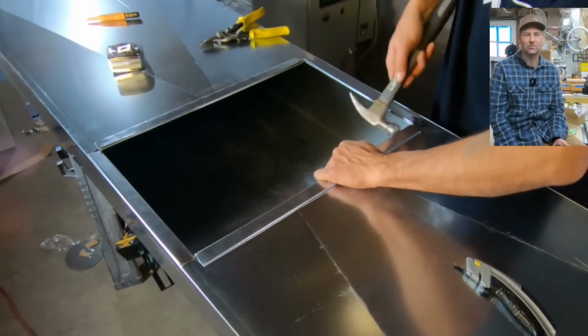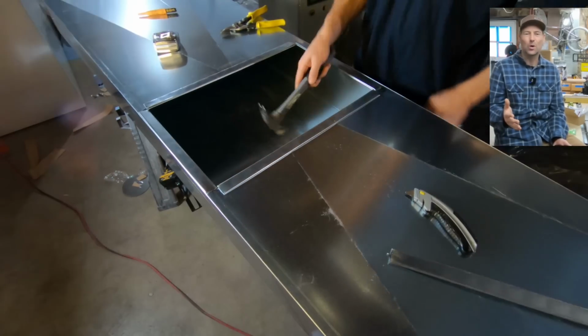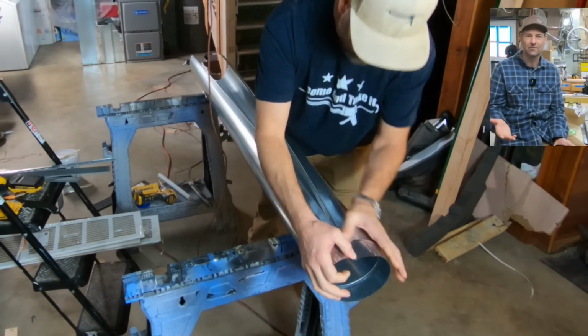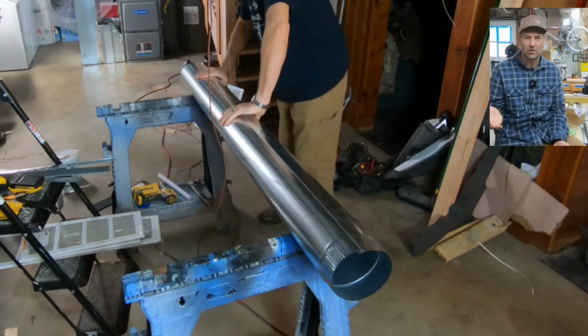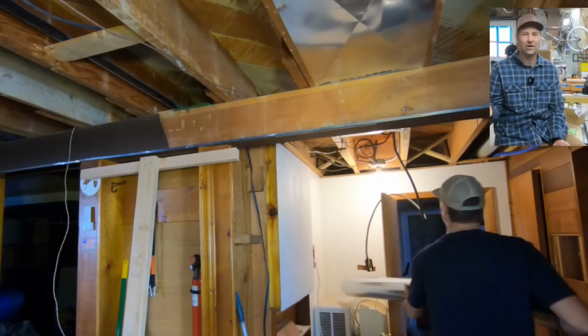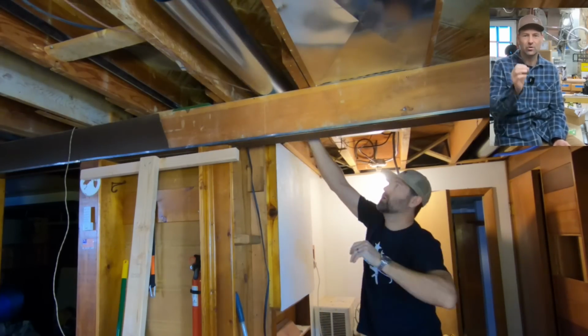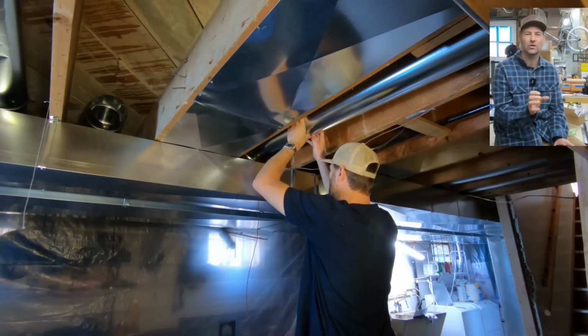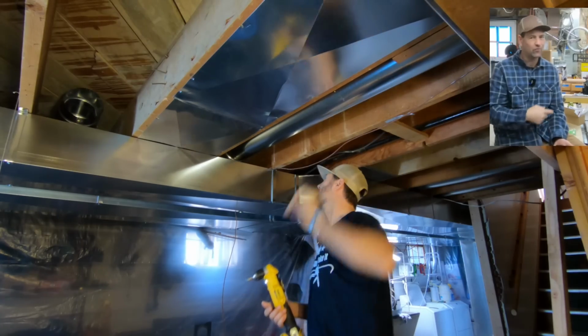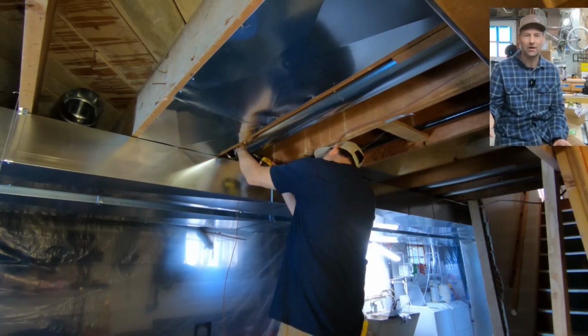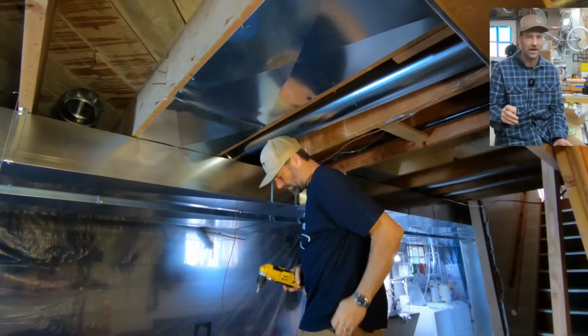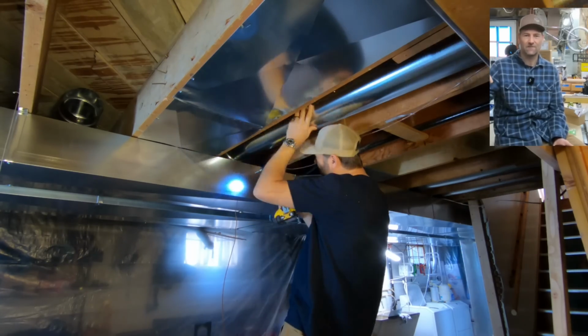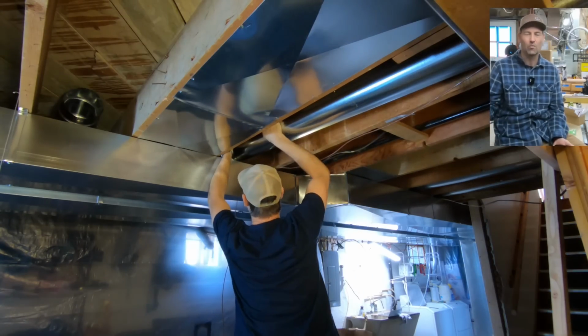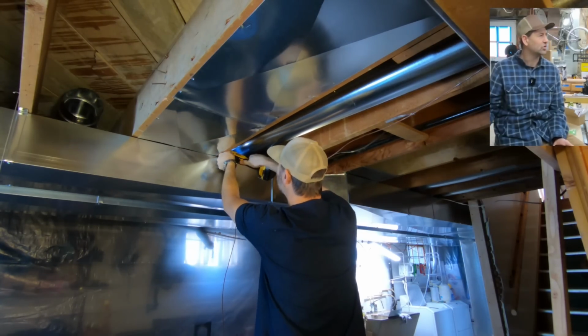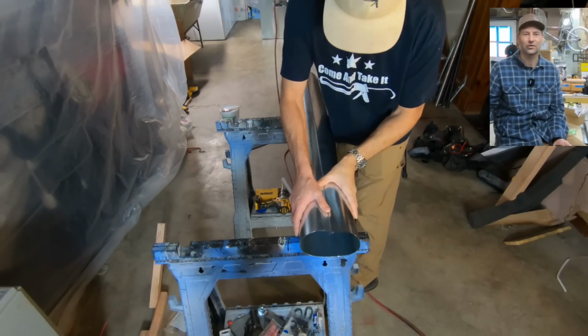Back when I was building houses, oftentimes we did it in the winter. And how do you heat a house in the wintertime when you're installing drywall? Most of the drywallers would just jumper with a nail or a piece of wire the R and the W inside a furnace, and they would run the furnace full blast 24 hours a day during the joint compound process. It was a horrible thing. They were not supposed to do that. What happened is a lot of those furnaces failed within the first year of home ownership because they were run full blast, no furnace filter, during the drywall tape and joint stage.